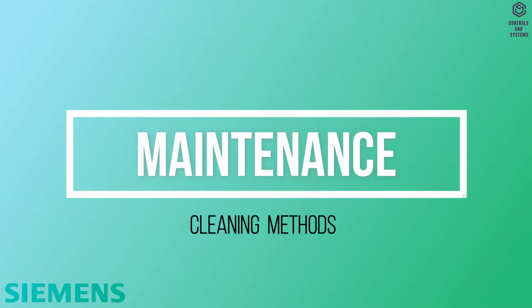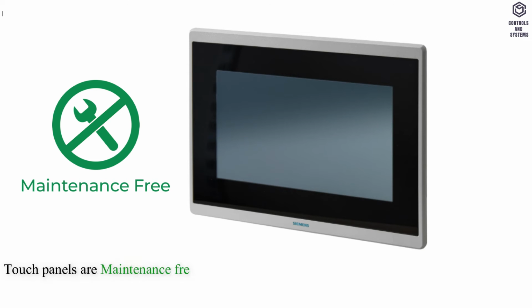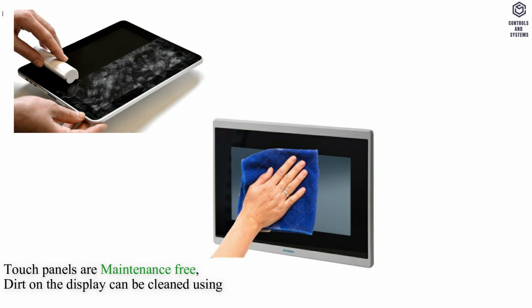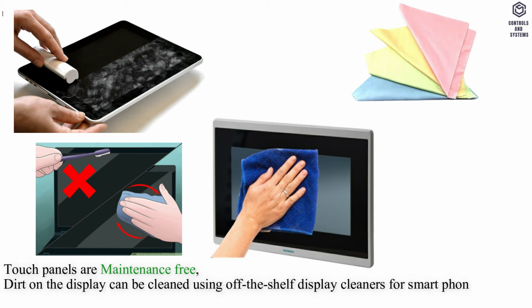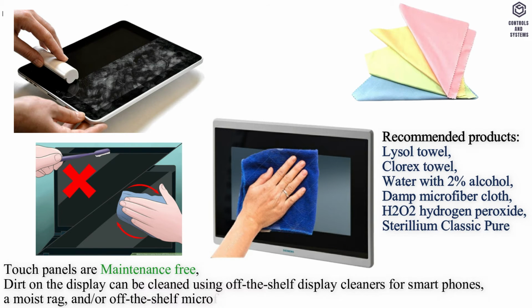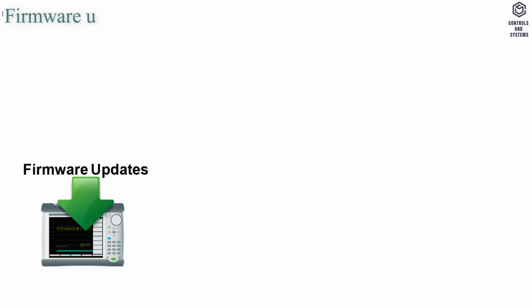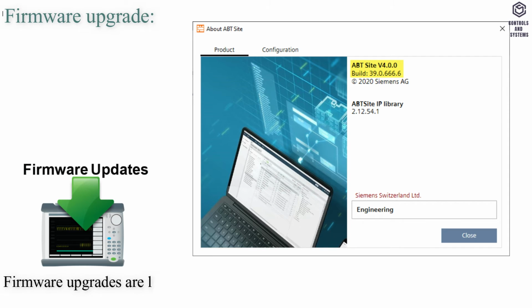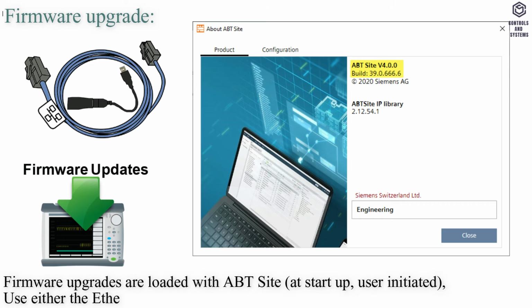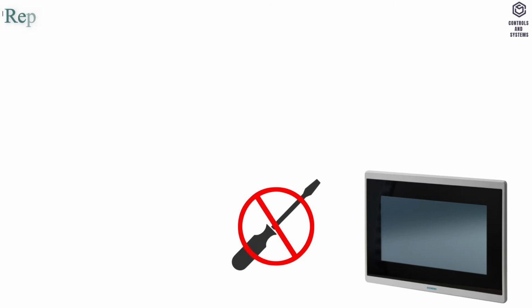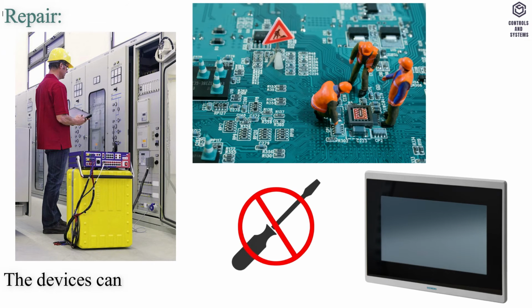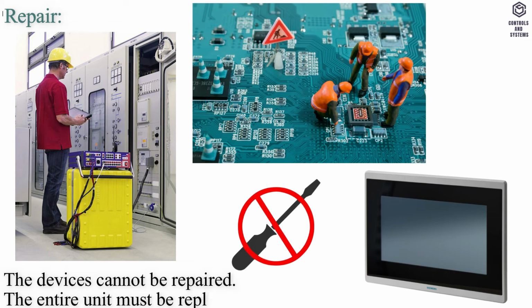Maintenance. Touch panels are maintenance-free. Dirt on the display can be cleaned using off-the-shelf display cleaners for smartphones, a moist rag, and/or an off-the-shelf microfiber cloth for monitors or glasses. Firmware upgrade. Firmware upgrades are loaded with ABT site, at startup, user-initiated. Use either the Ethernet or USB interface. Repair. The devices cannot be repaired. The entire unit must be replaced.